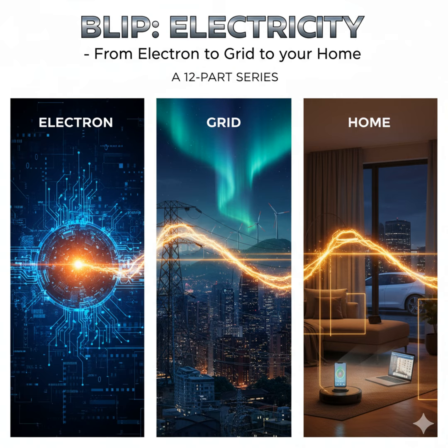Worse than waste, actually. It causes a significant voltage drop along the line. The further you try to push Q, the lower the voltage gets at the receiving end. Try to push it too far or push too much, and the voltage can collapse entirely. Collapse, like the lights go out, the motors stop. Exactly. A voltage collapse. It means the system can no longer maintain adequate voltage to supply the load. So trying to centralize Q generation and transmit it is basically impossible for a stable grid.